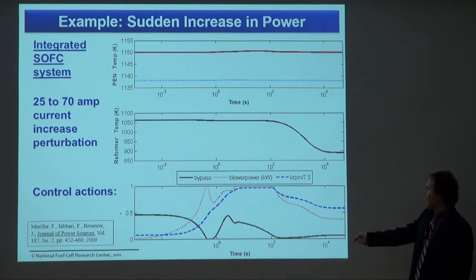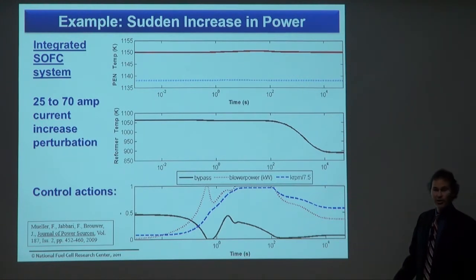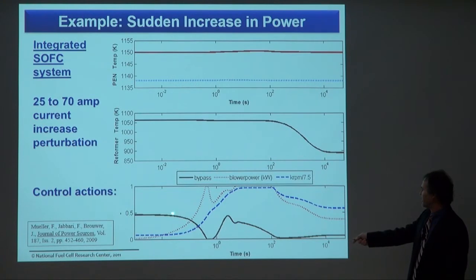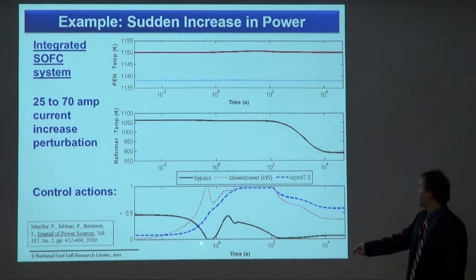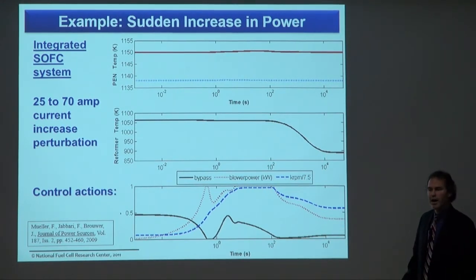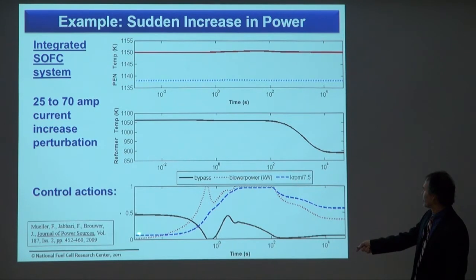These are the control actions my controller took in this case: I ended up taking the bypass valve down to fully closed for a while, then opened it up a little bit and settled at a much lower overall bypass. You can see the blower power changed in this particular way, and the blower speed changed in this particular way as well.